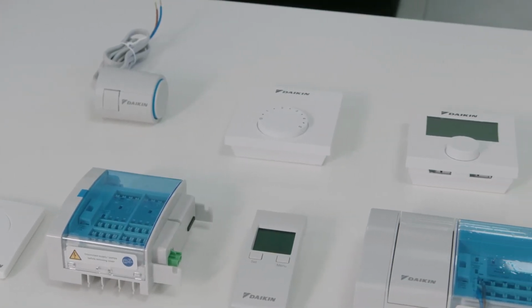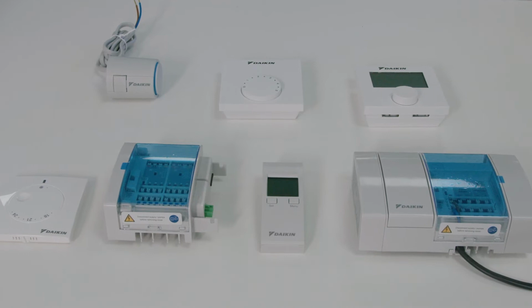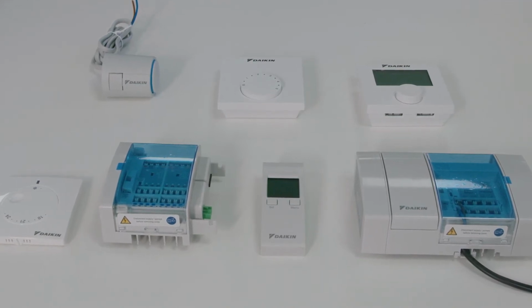Individual room controls enable the room temperature set by the user to be achieved in every room. As well as controlling the heat output of the actual heating surfaces, the room temperature controllers also sense all external heat influences such as solar radiation, lighting, and occupants' heat gain, or other heat sources such as an open fireplace or a stove. On the basis of constant target or actual comparison, the room temperature controller opens and closes the individual heating circuits via electric actuators. Today, room controllers are not only mandatory, but are necessary to provide users comfort and savings.